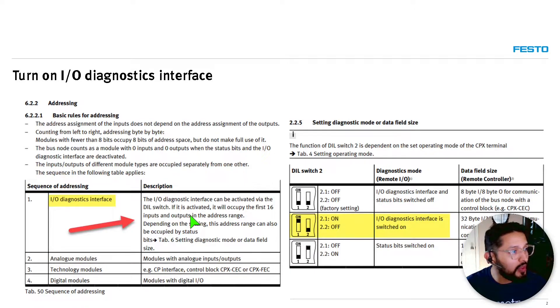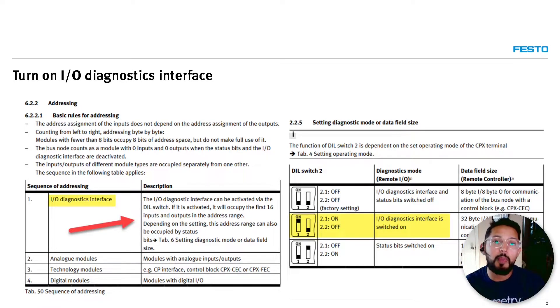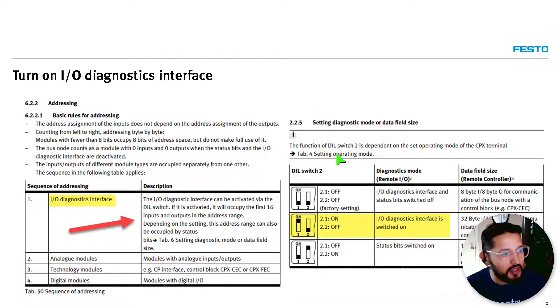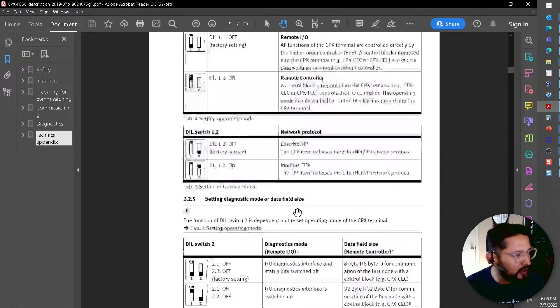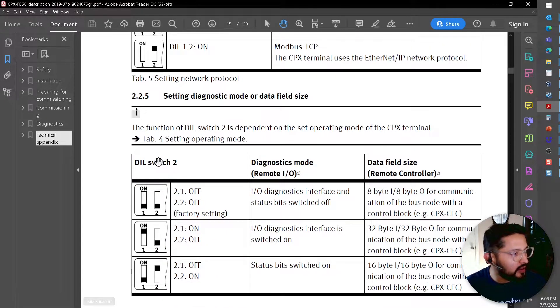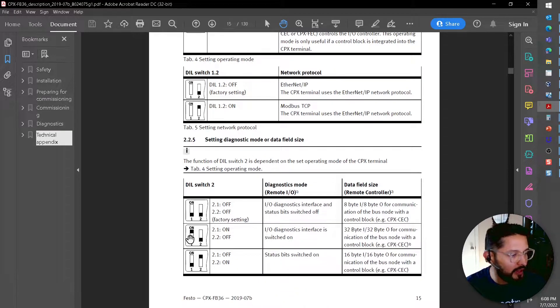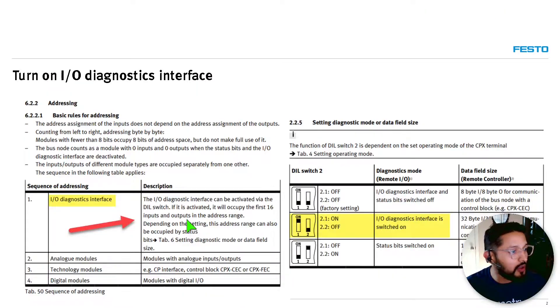The next step is to turn on the IO diagnostic interface. This is useful because it gives you two additional bytes of data you can use to pull information out of the CPX — which is exactly what we're doing today to pull the module code. To enable it, we use DIL switch 2: switching on the left one enables the IO diagnostics interface.